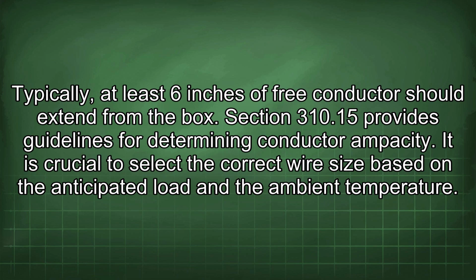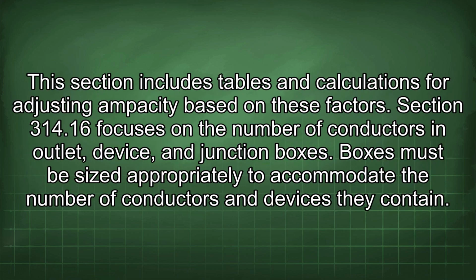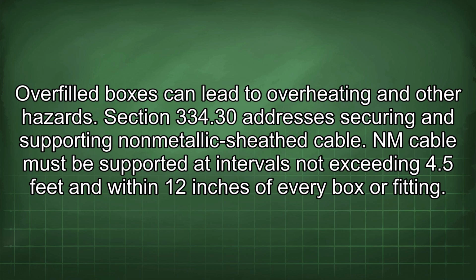It is crucial to select the correct wire size based on the anticipated load and the ambient temperature. This section includes tables and calculations for adjusting ampacity based on these factors. Section 314.16 focuses on the number of conductors in outlet device and junction boxes. Boxes must be sized appropriately to accommodate the number of conductors and devices they contain. Overfilled boxes can lead to overheating and other hazards.